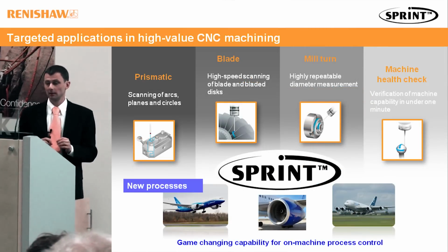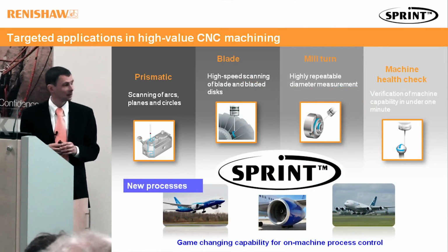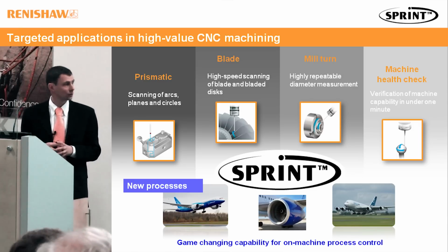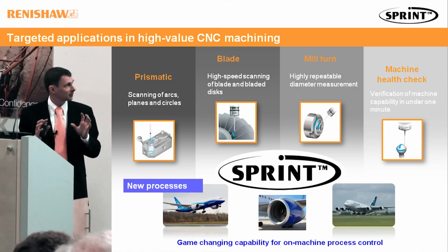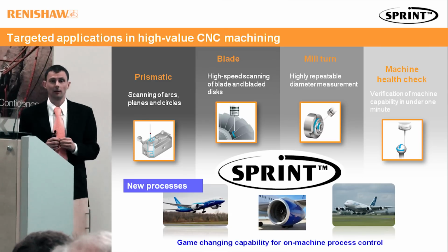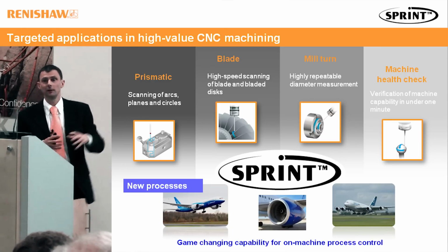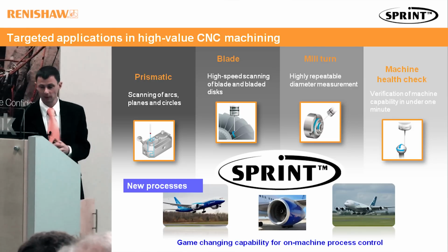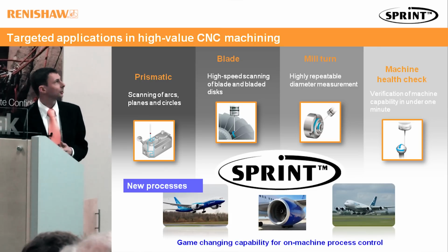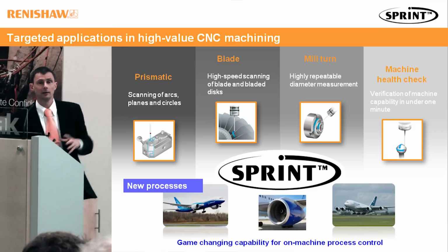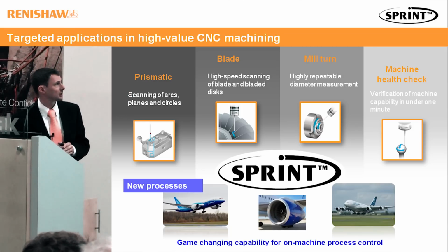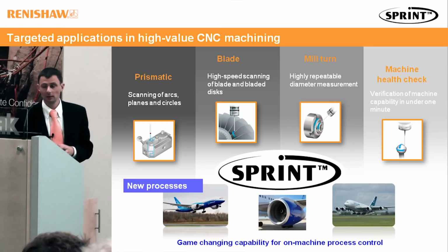The Sprint system is targeted at high-value CNC machining, and it's targeted for process control. We released the functionality in 4 key areas. Firstly, our standard prismatic feature measurement functionality, which is the standard functionality of the system for measuring circles, arcs and planes. And then additionally, we have 3 specific application toolkits for very specific tasks. The first is a blade measurement toolkit. The second is a mill turn for highly repeatable diameter measurement. And the third is a very fast verification of machine capability, what we call a machine health check.